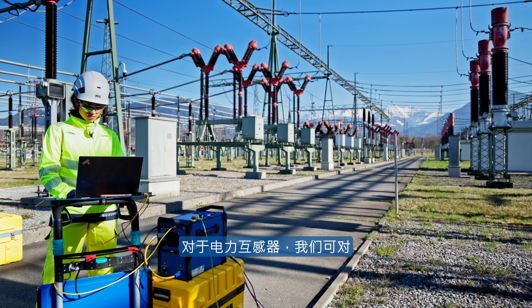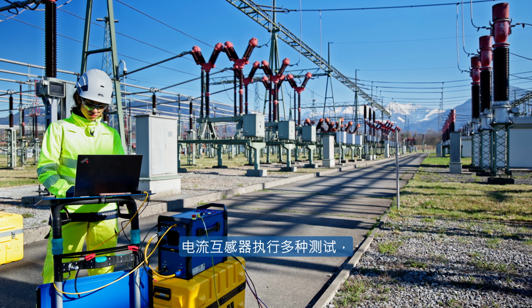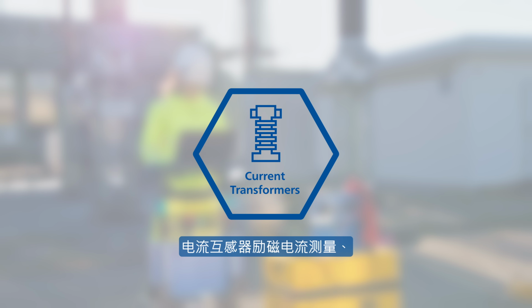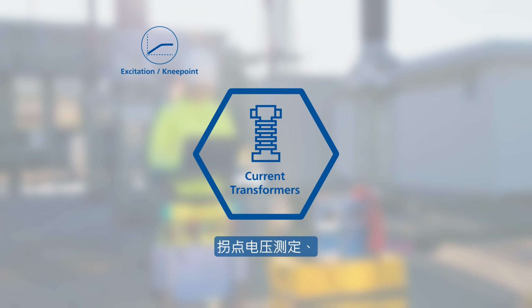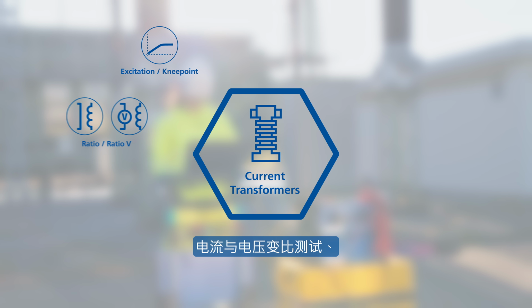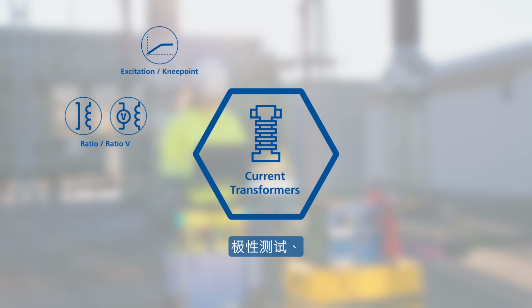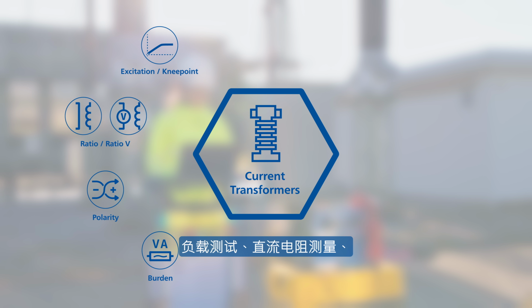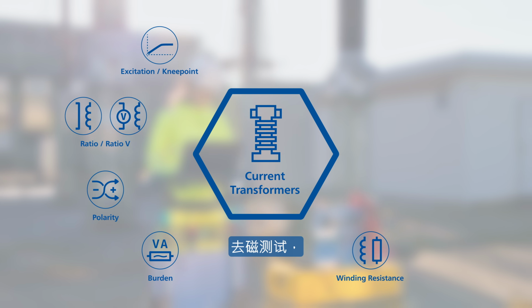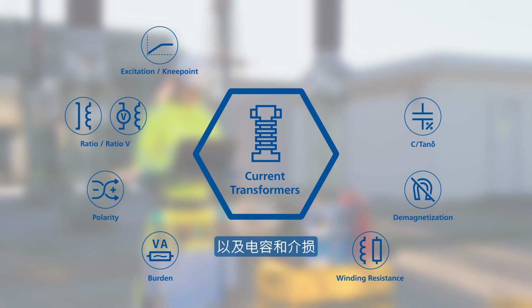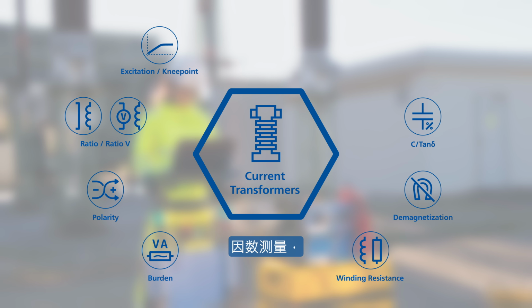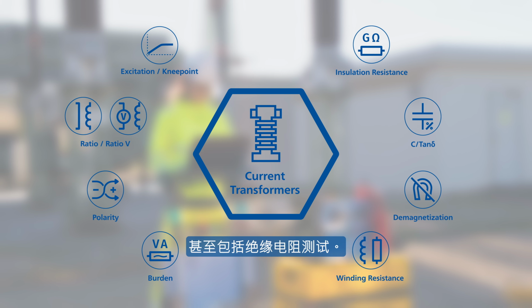On instrument transformers, we can perform a wide range of tests on CTs, including CT excitation current measurements, determining the knee point voltage, ratio tests with both current and voltage, polarity tests, burden tests, DC resistance measurements, demagnetization tests, as well as capacitance and dissipation factor measurements, and even insulation resistance tests.